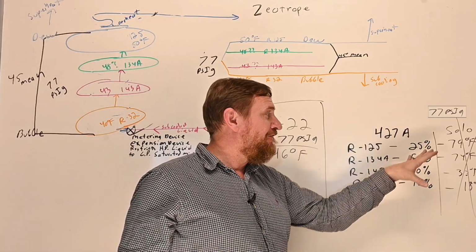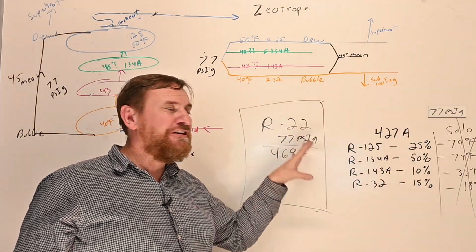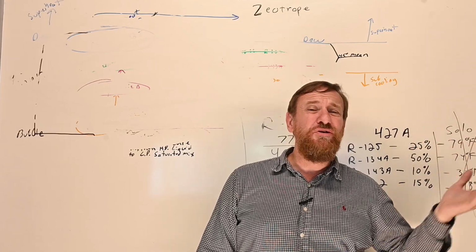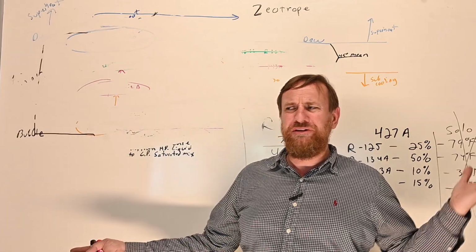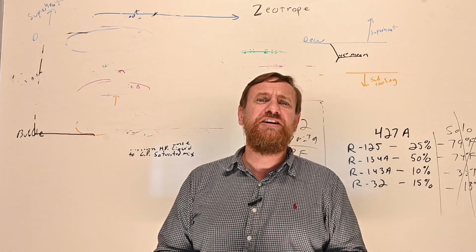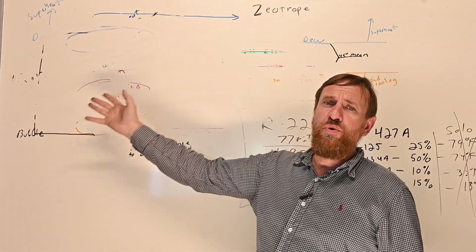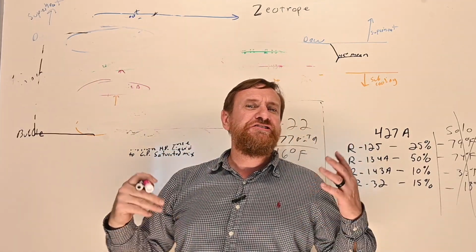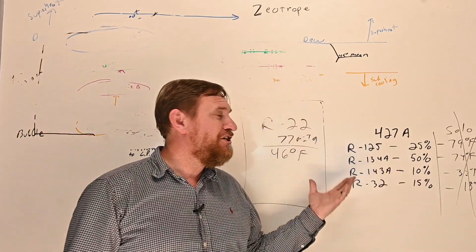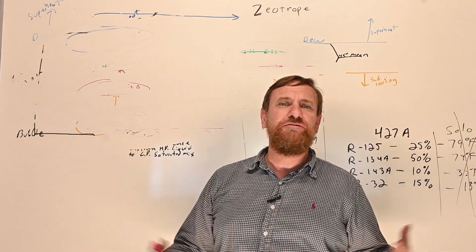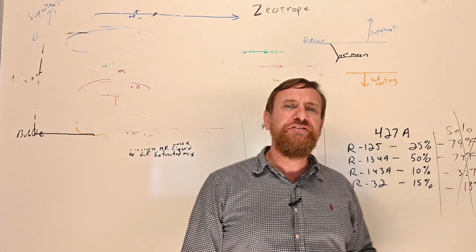the window. Now, if we change this with even another refrigerant, a 5th refrigerant, R22 is already there. If you're going to mix refrigerants, at least put a tag in there so the next man or woman coming along can actually know what is happening inside that system, and they're not going to be looking at their superheat and subcooling and thinking, man, everything is off. This doesn't make sense at all. And at least the next person can have the choice of recovering all that refrigerant so they can protect that compressor. But if you understand the refrigeration cycle, if you understand saturation and these mixtures, mixing refrigerants is a complete killer. It just ruins everything we work for in this whole entire system.